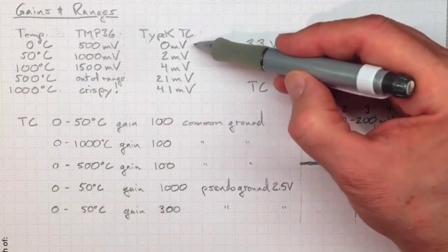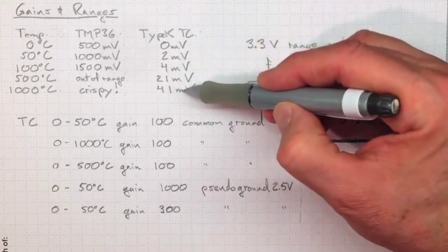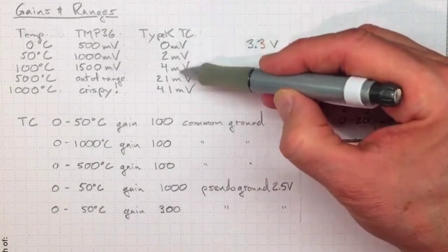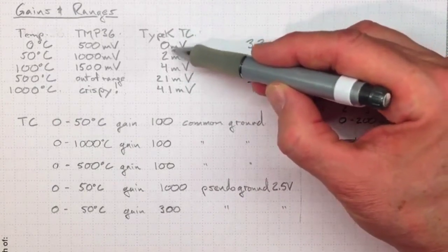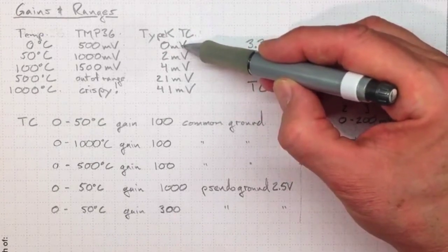A type K thermocouple gives us a much lower voltage output, going from zero up to about 41 millivolts over that thousand degrees Celsius range. Depending on where we're trying to measure in that range, down in the low temperatures or up to higher temperatures, we'll choose different input ranges and gains.